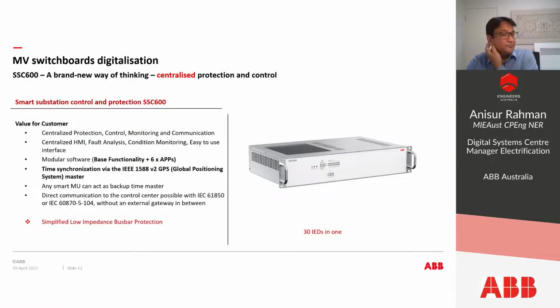Here we use our most innovative SSC 600, a brand new way of thinking. It is actually centralized protection and control. You can think of this device as one device that includes 30 IEDs. So it provides the backup protection for 30 bays, as well as the busbar differential protection. The main driver to choose this one is its simplified low impedance busbar protection.